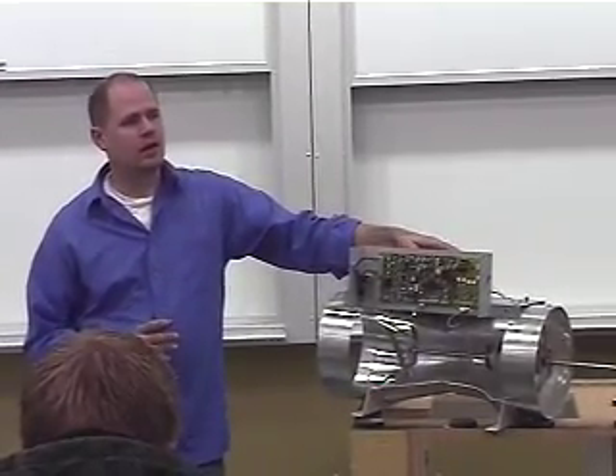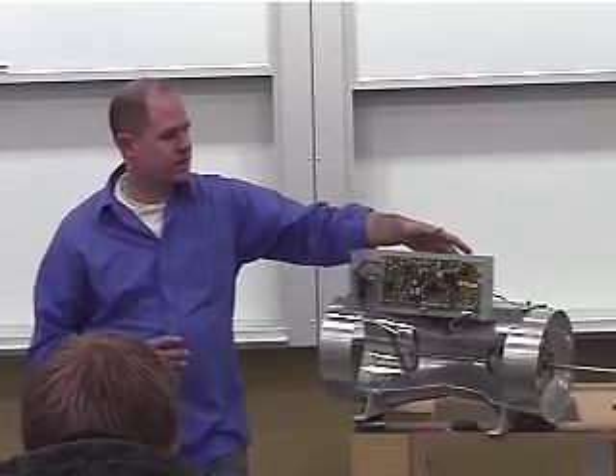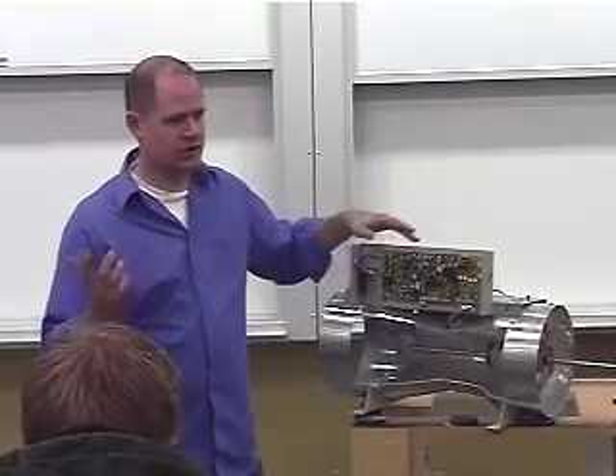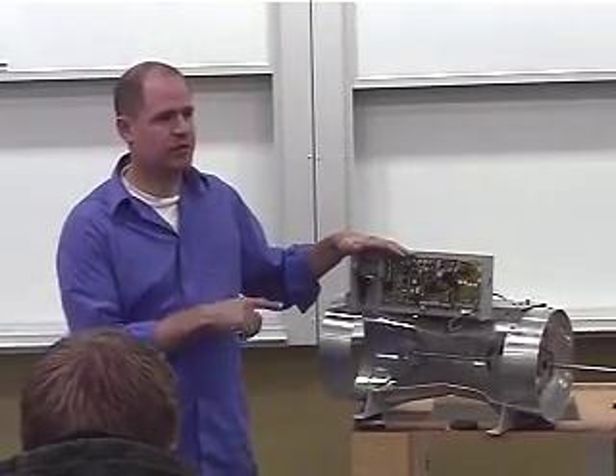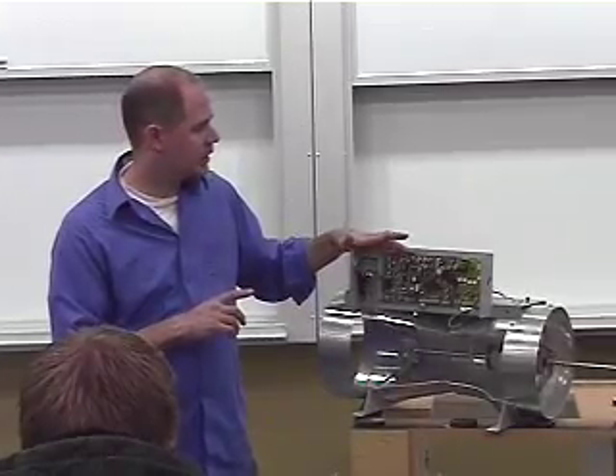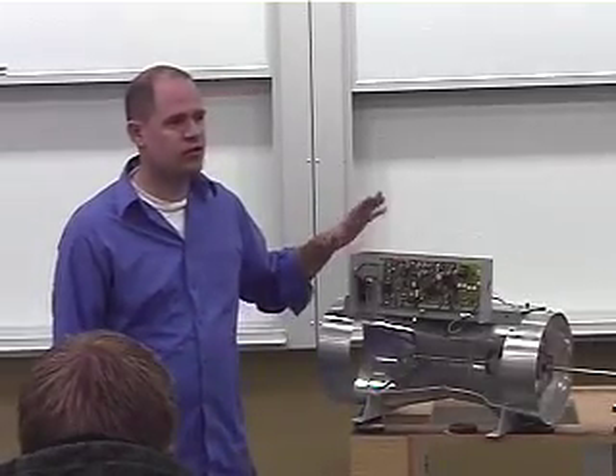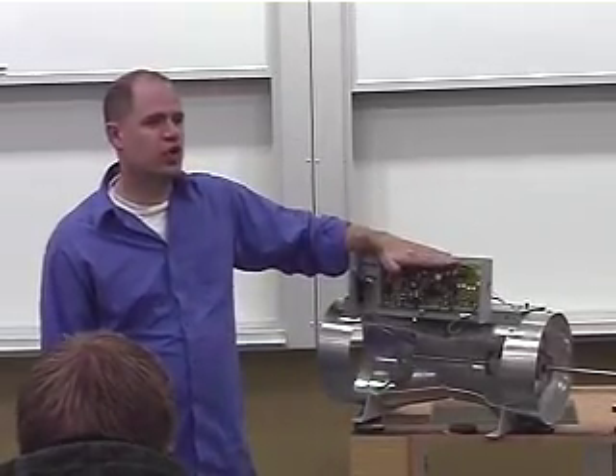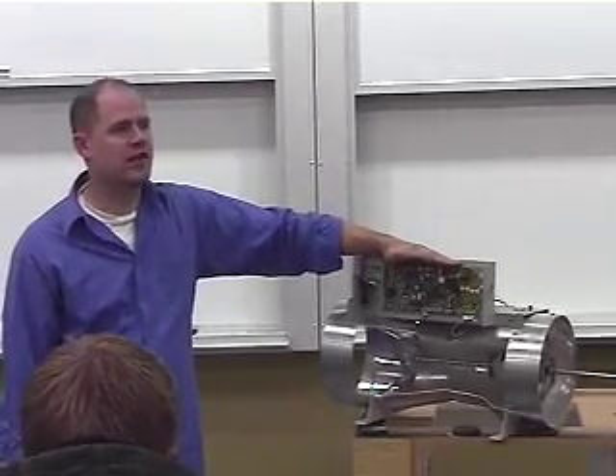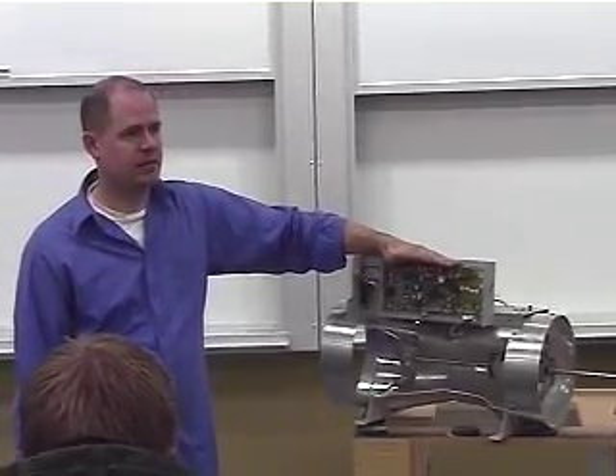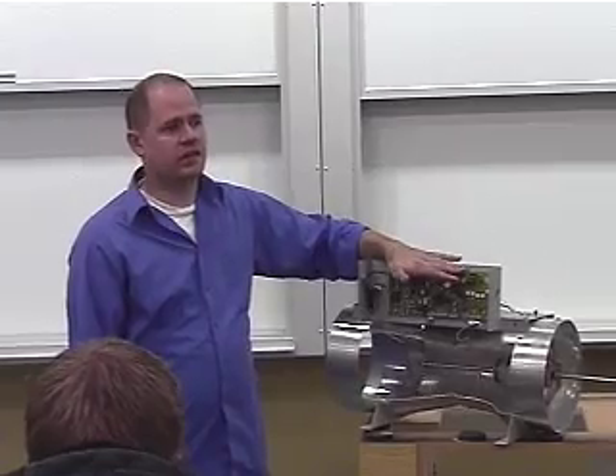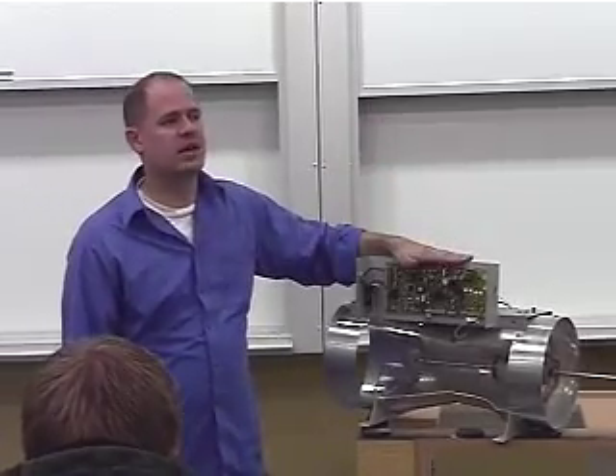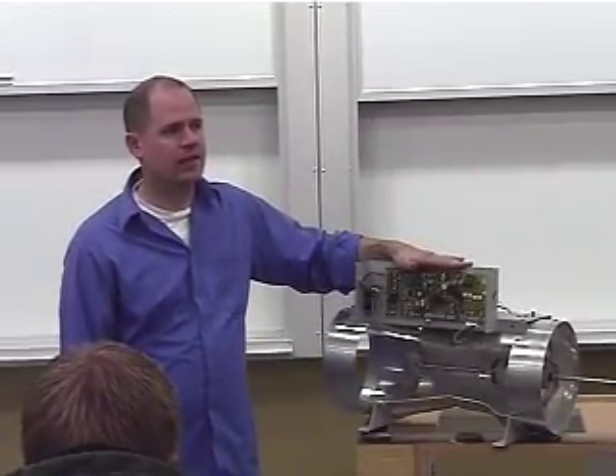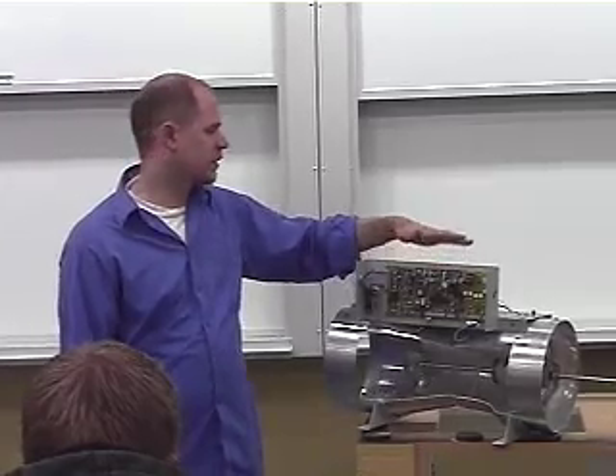What about the boards, if they fail? The circuit boards, if they fail, those are covered for the same warranty period as all the other parts. And typically we can just get another one of those and swap them out. The board stores the flow curve for each of these valves. So they have individually set up flow curves based off the serial number? Yes. And the flow curve we can reload to any board and throw it on there. And the flow curve is stored based off the serial number of the valve.